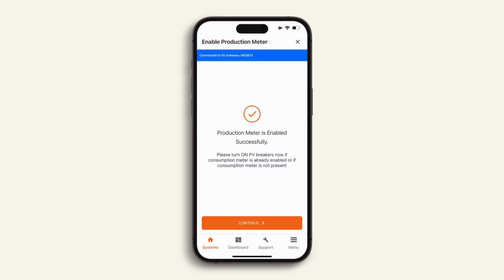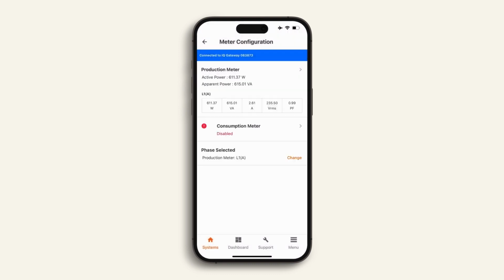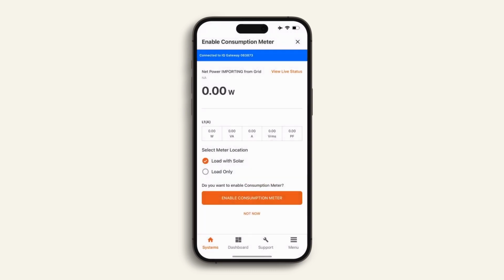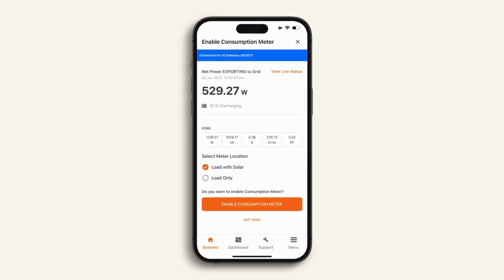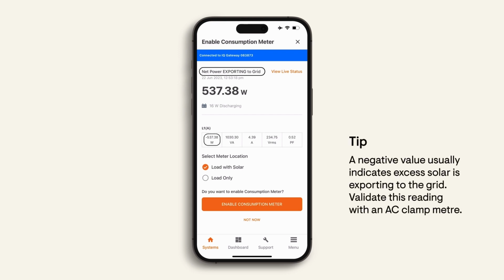Production metering is set. Now let's complete consumption metering. We will now commission and enable the consumption meter. First select the phase number. And again, in this example, I'm selecting No, I'm an expert. Although the meter is pre-wired, you will need to select the meter location, which will be Load with Solar for all Australia and New Zealand installations. Now enable the CT. Keep checking the measurements. The power reading in this example is now showing exporting to grid and negative values in the power readings. You expect to see a negative value when the solar is exporting power to the grid.